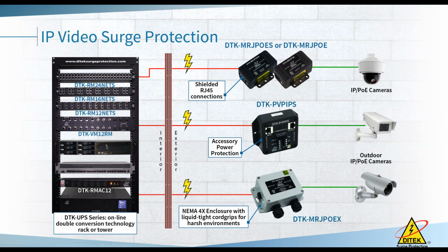If you were to take that same cable, unhook it from the camera, and put a phone out there on that pole, now you'd have to cover it with surge protection. So that's an easy way to tell customers: if this thing were a phone on a pole, I'd have to have surge; I just changed it to a camera, now I don't have to. Something to keep in mind. A lot of people, when you explain it that way, it's eye-opening.